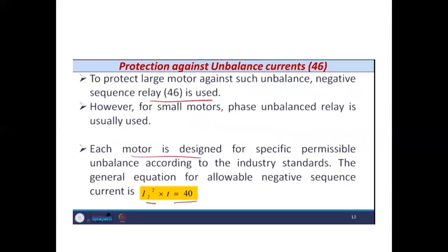However, for small motors, a phase unbalance relay is usually used because it is economically not viable to use the negative sequence relay.